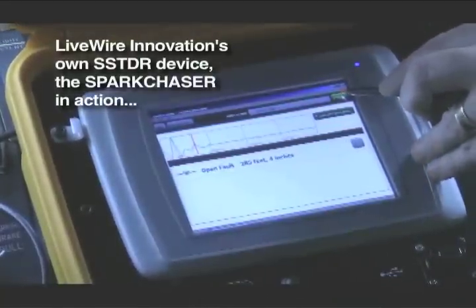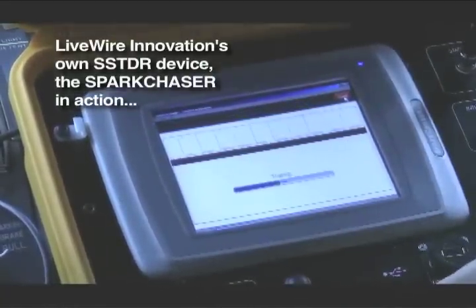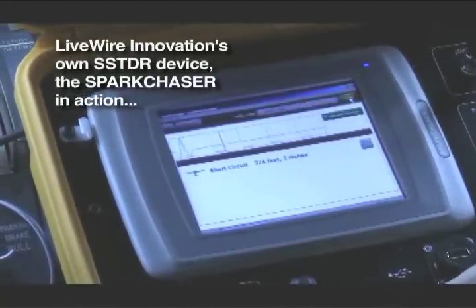Now let's come back to the faulty wire in your electrical system and combine SS technology with TDR technology. Take a single TDR signal and break it up into thousands of smaller signals, each with a different frequency making it immune to noise and other electrical disturbances. When the individual spread spectrum signals return, they combine to create a very accurate diagnosis.